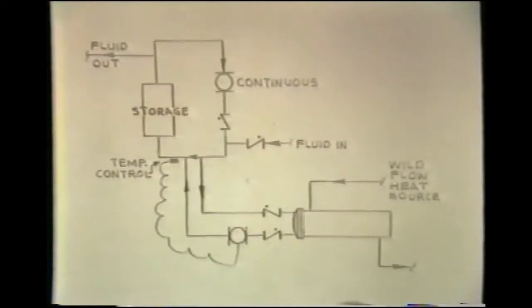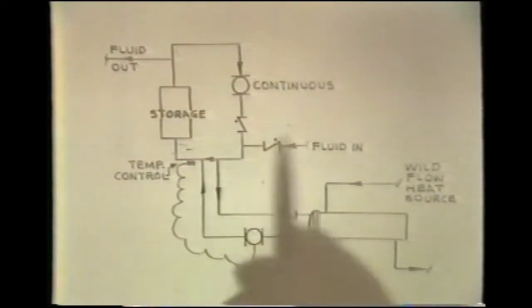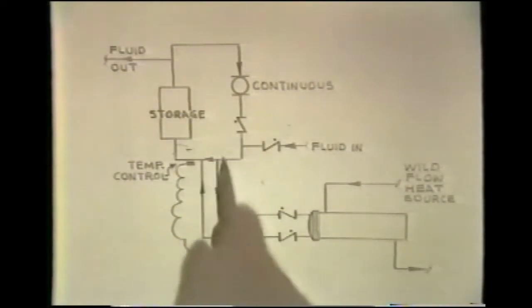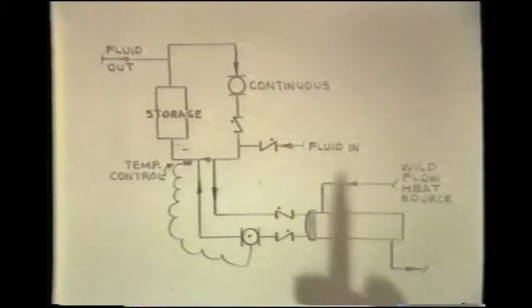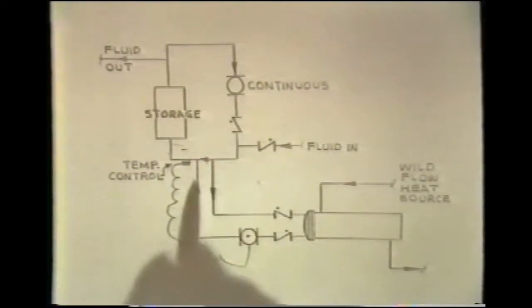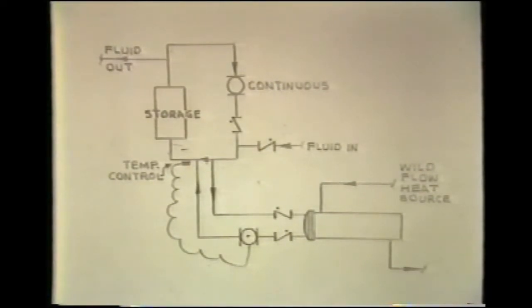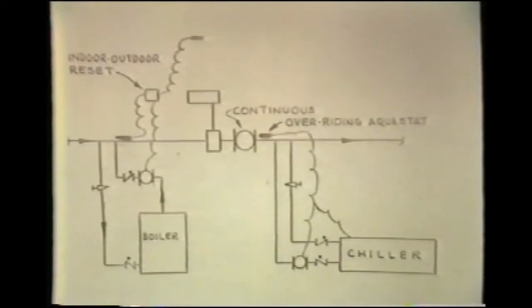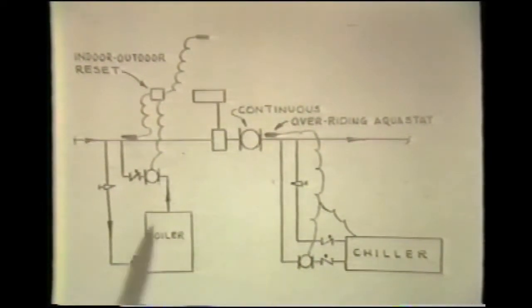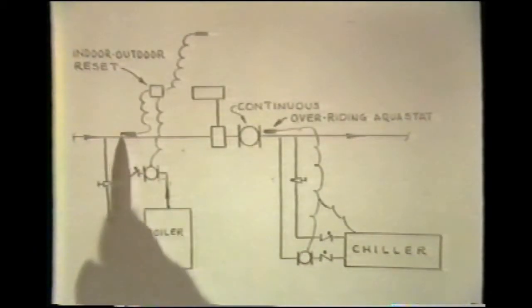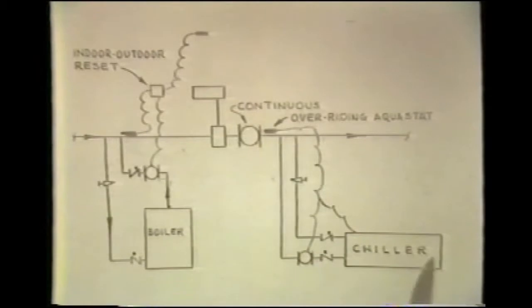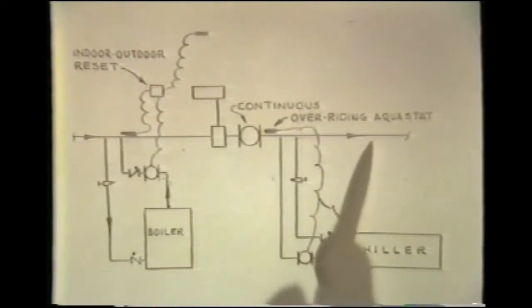Another application that has been widely used, many times in terms of storage, is to provide a storage tank pump with an injection pump running from a heat exchanger into the pumped loop for the storage tank. And again, we can establish extremely close and tight control for a system utilized in this manner.